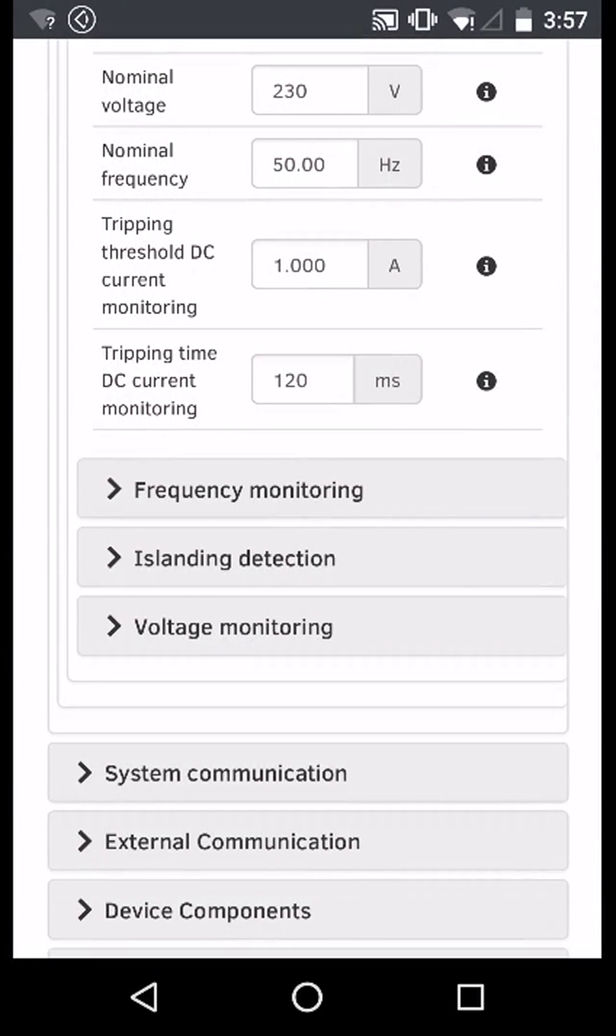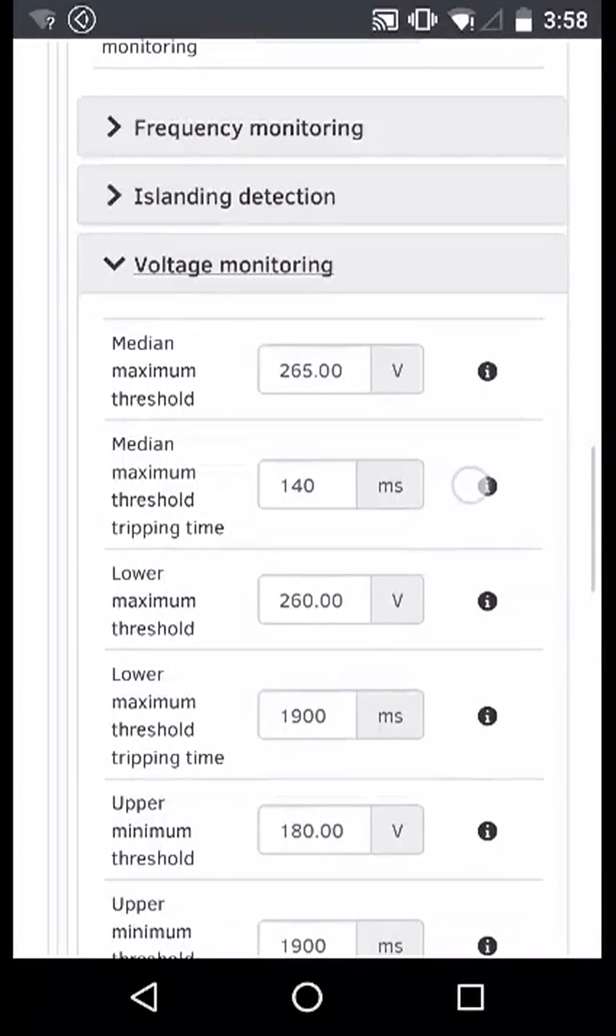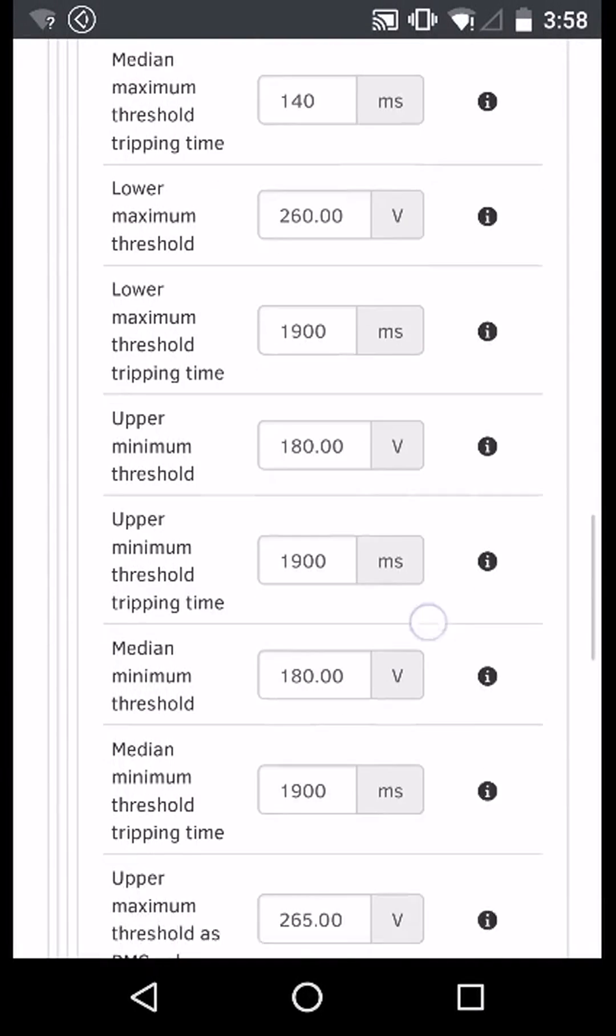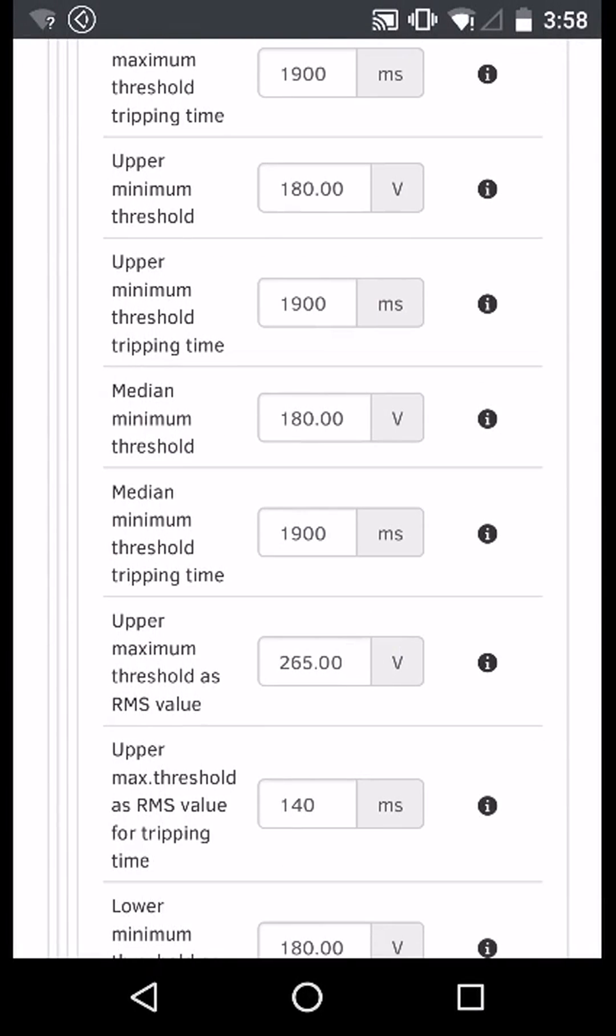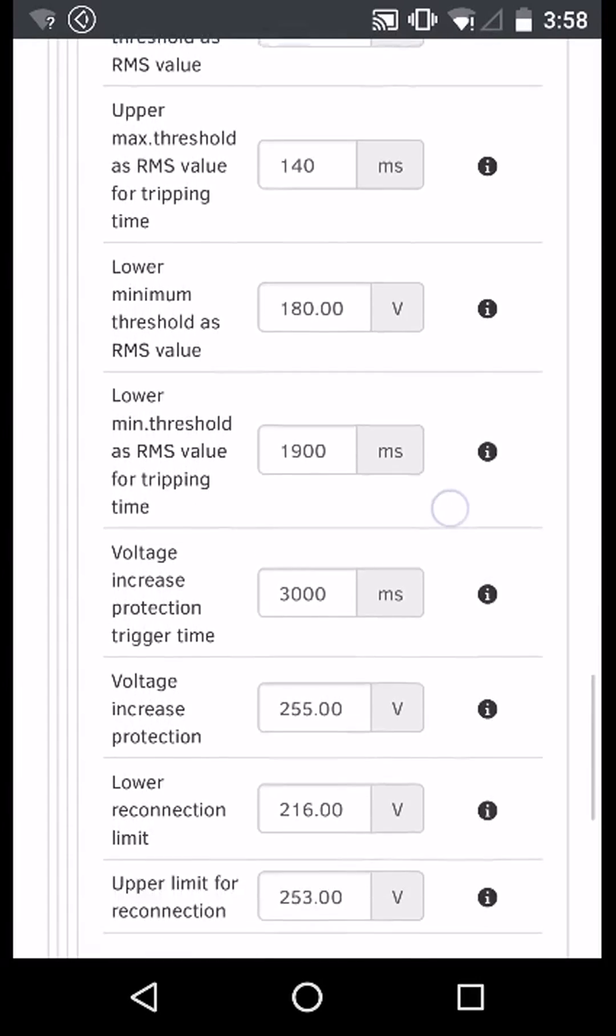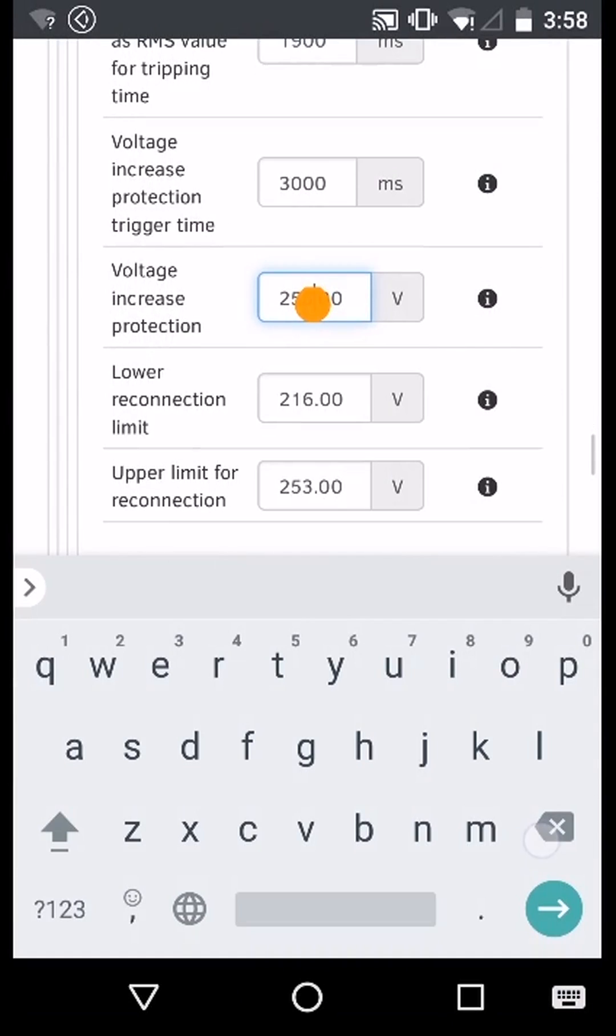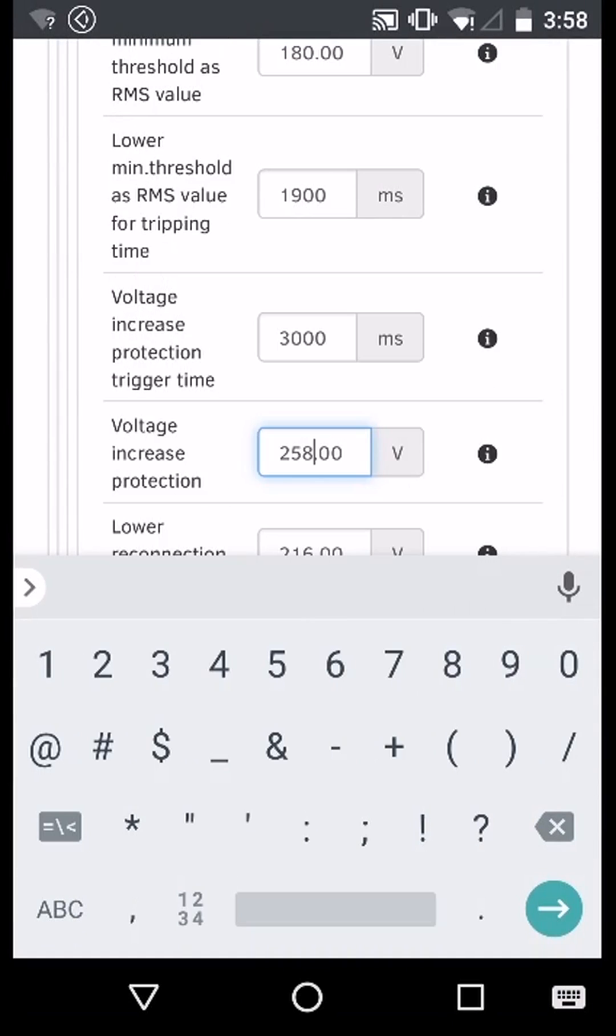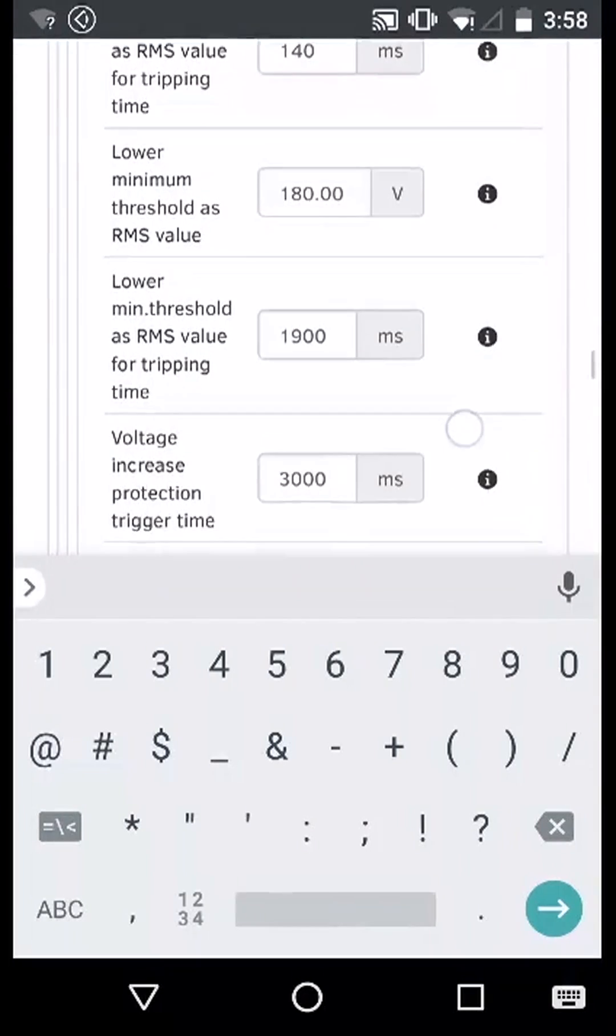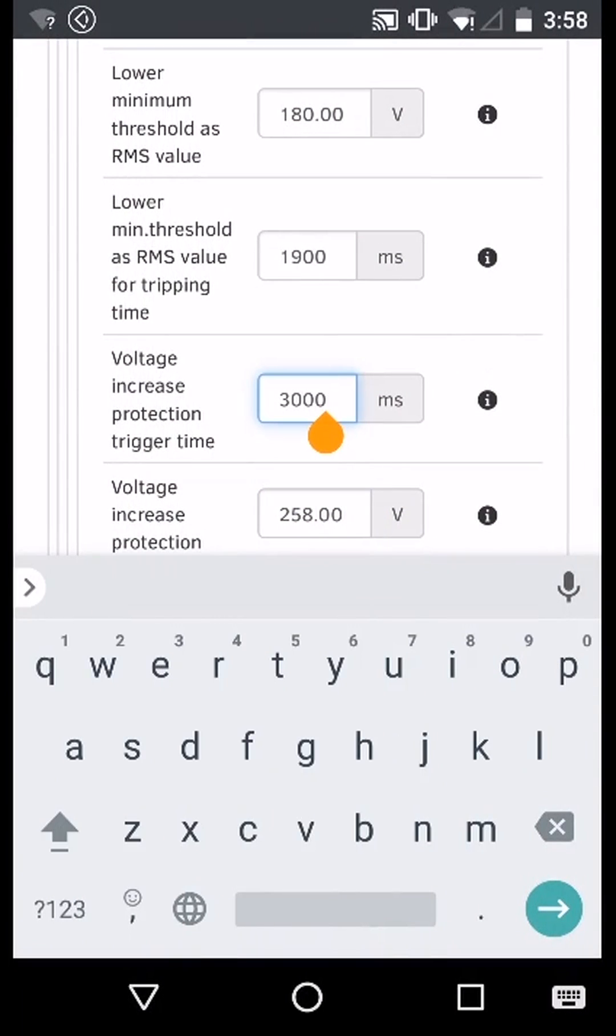Select the tab and this will open a list of parameters. We want to change voltage increase protection to 258 volts and change the trigger time to 3000 milliseconds.